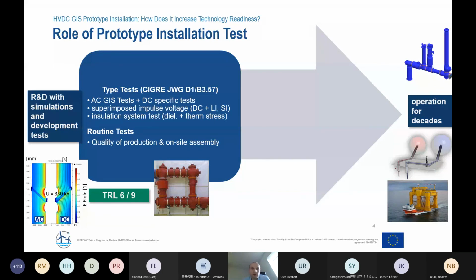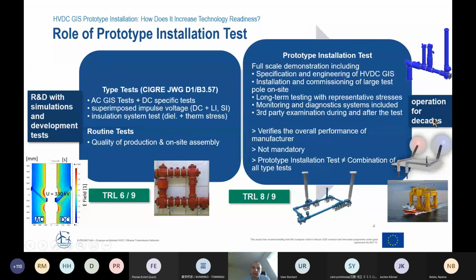But from the user side and from the operational experience side, there's still somehow a gap between these type tests and the reliable operation in the field. And what we try to do within PROMOTION is to bridge this gap from the somewhat lower technology readiness level to the real-world application by means of a prototype installation test. And this is basically a full-scale demonstration that includes not just the testing, but also the specification and the engineering of an HVDC GIS, like it would be done in a real project.